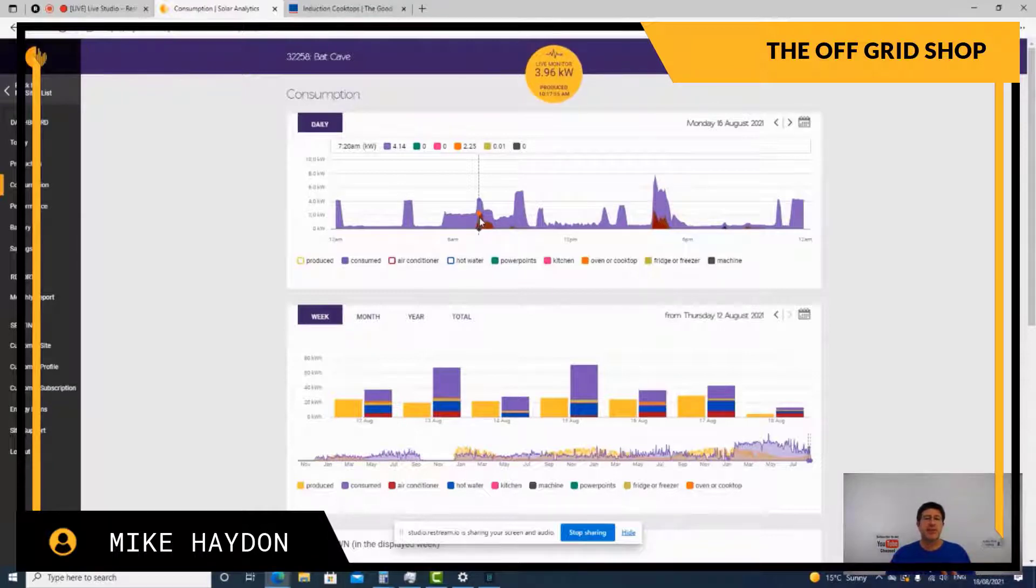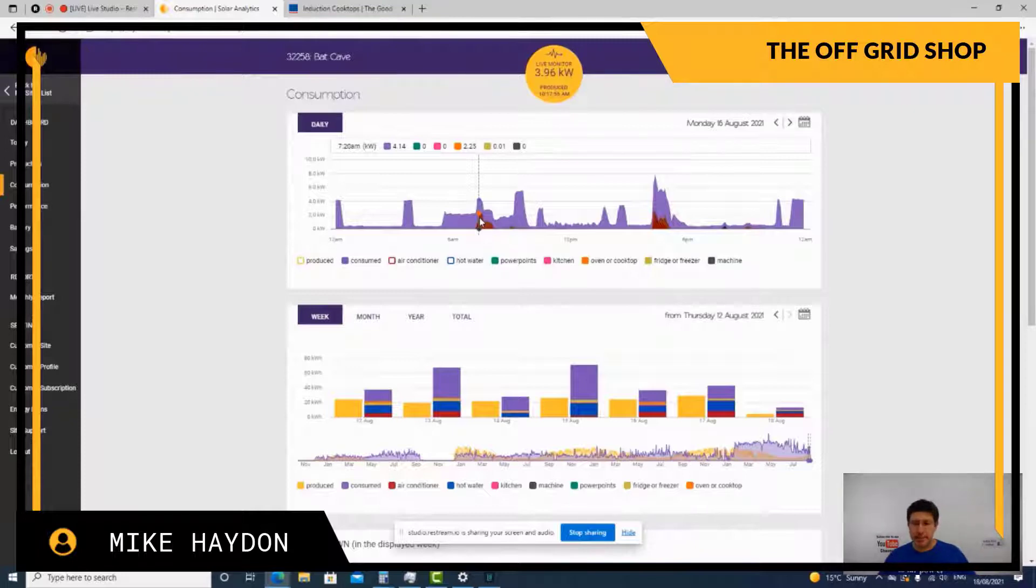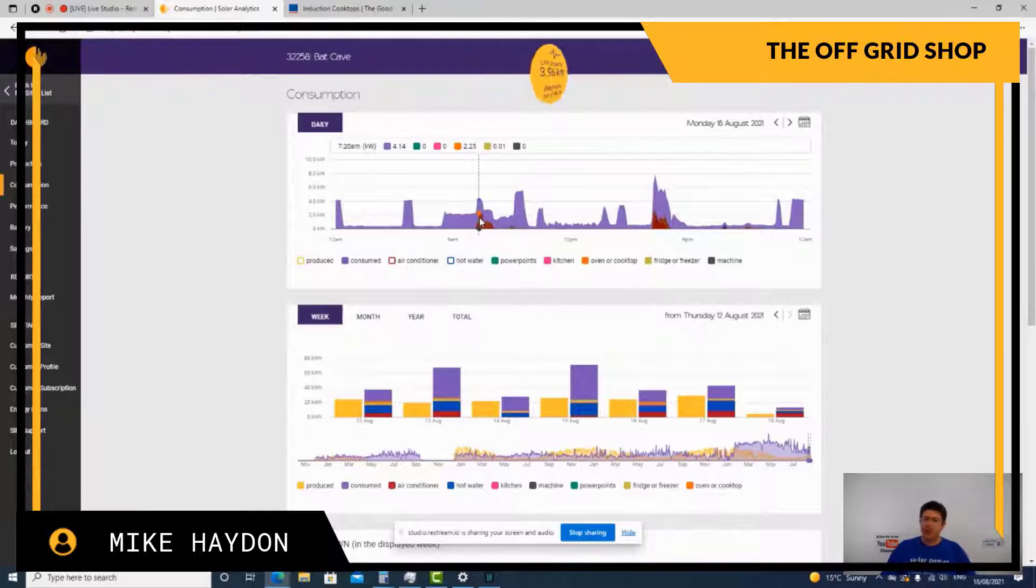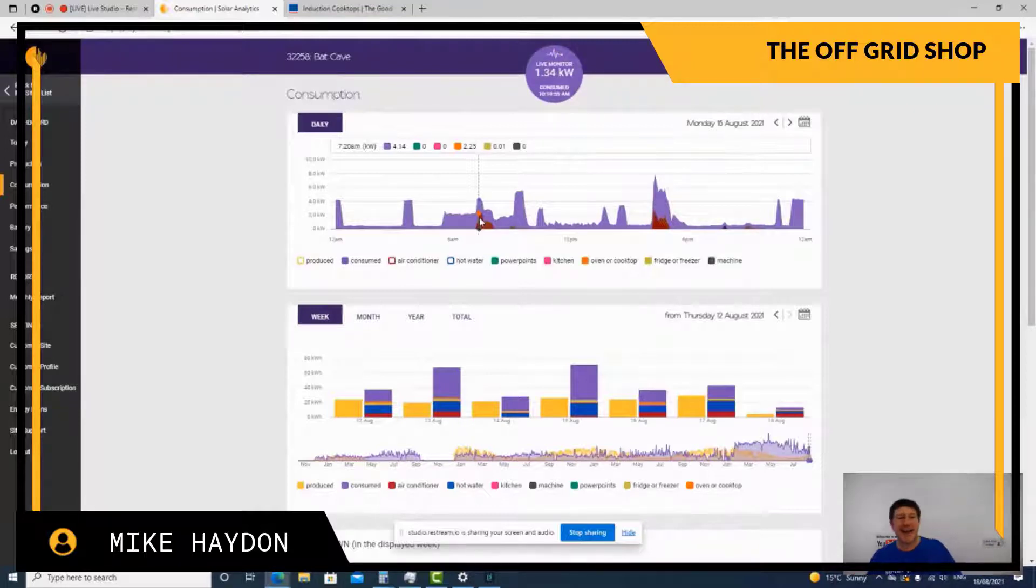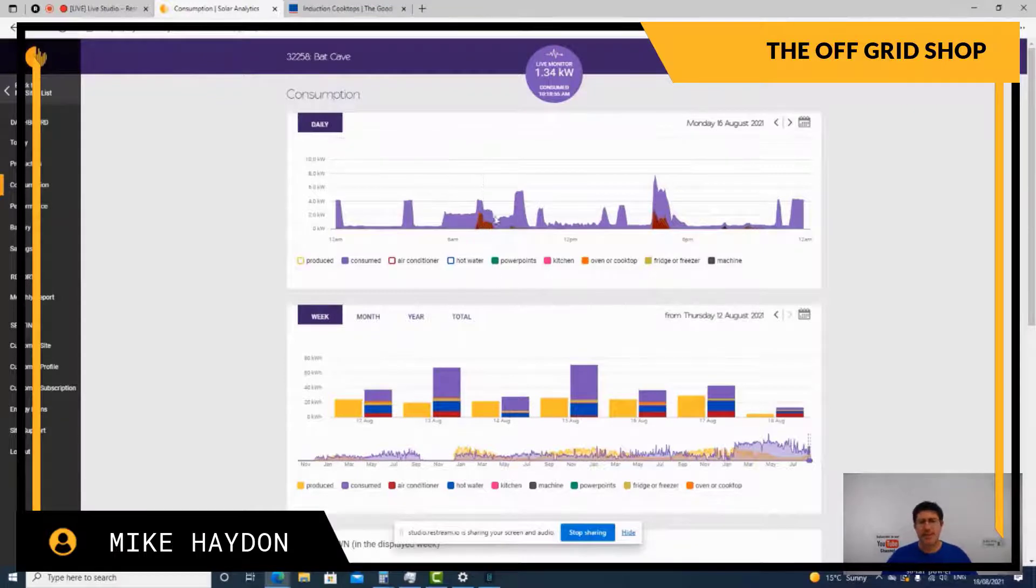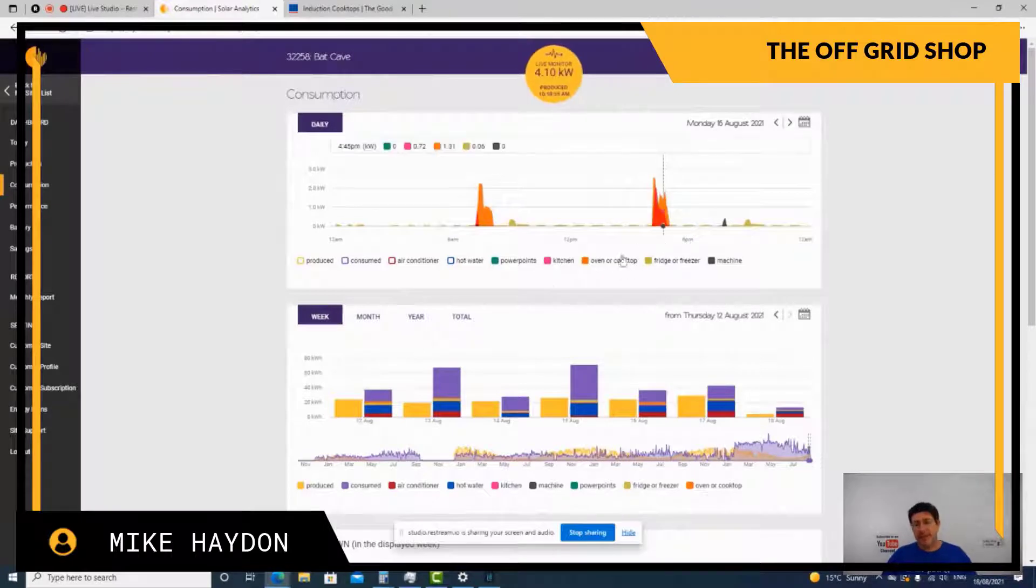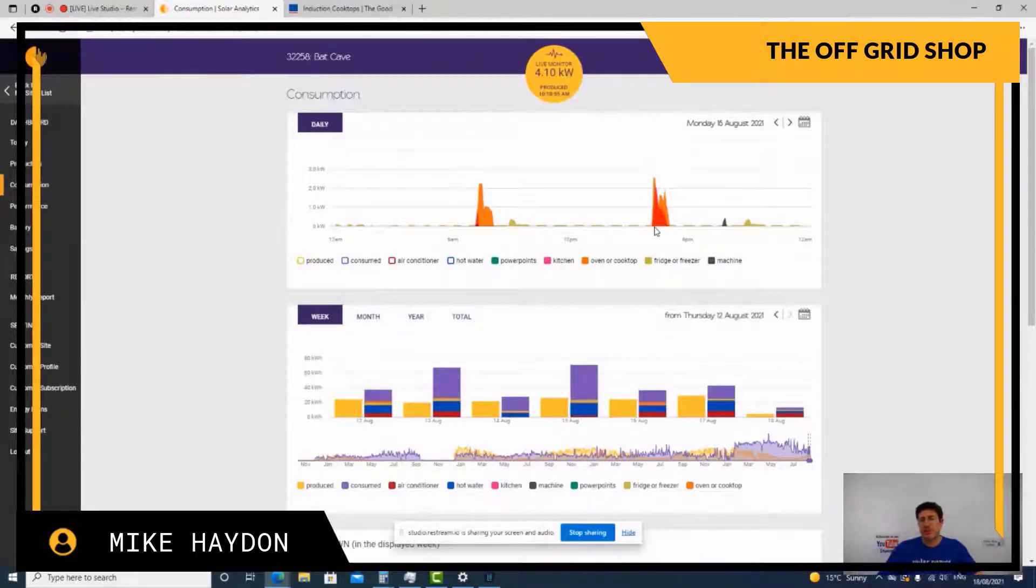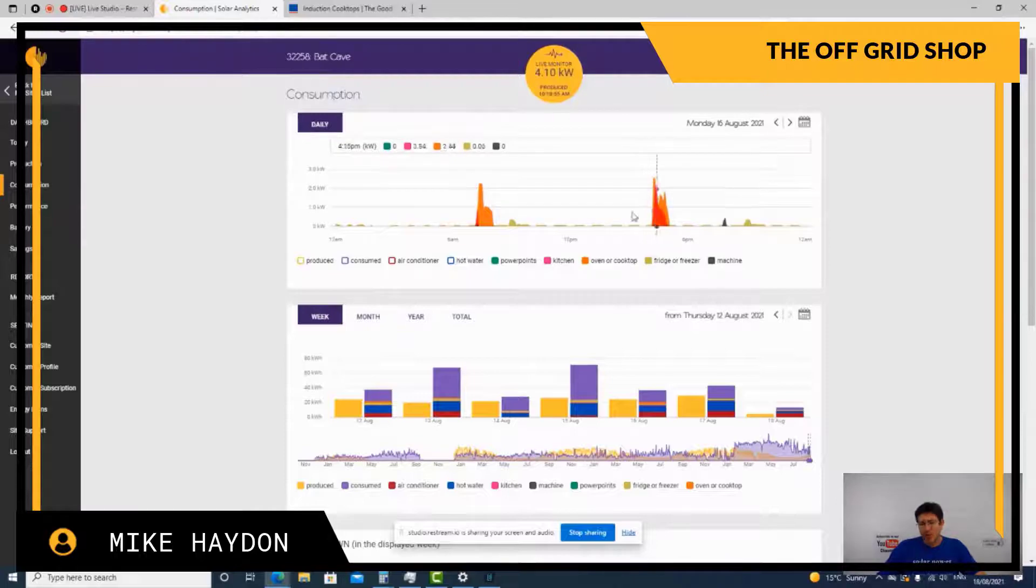Now, if you're looking to size an inverter in an off-grid situation, a 5 kVA inverter, you'd be really pushing the limits in this moment of doing this. I'd probably recommend going eight as a minimum. That's pretty much what most suppliers do off-grid. They sort of do a four to a five, and then pretty much everyone goes up to an eight. So something to think about. And actually have a look at the specifications of the data sheet of how long it'll actually run those loads for. As you can see there, it's pulling 4000 watts around at once. So we'll jump over in the afternoon, look at the afternoon, which is where we're using more of the cooktop.